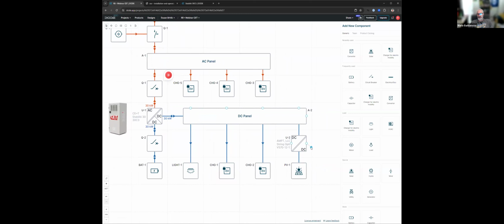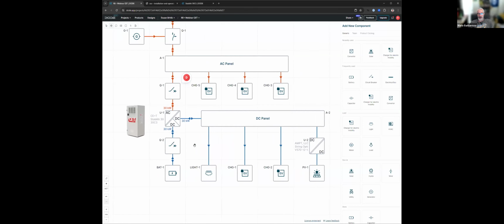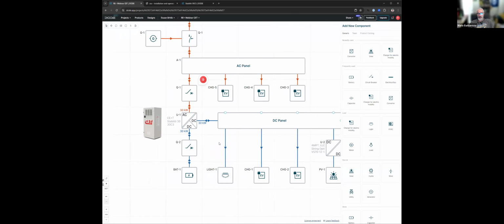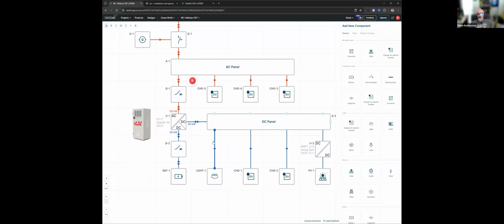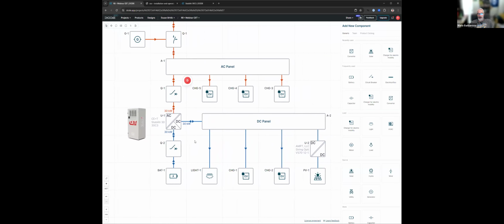If your state of charge is 60%, of course you're not going to curtail - you have to maximize your battery state of charge. Most of our customers go to 80%, and then at 80% they reduce the charge rate. But there are situations where there's no EV to charge, or the lighting system has constant demand, so that's why you need that type of control.